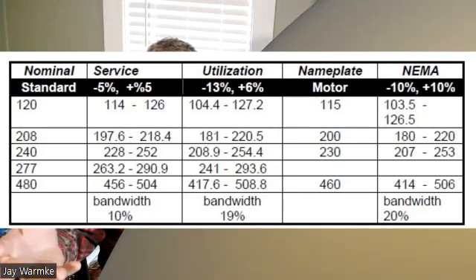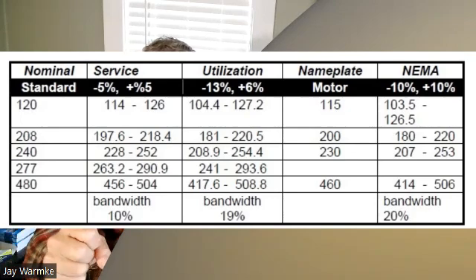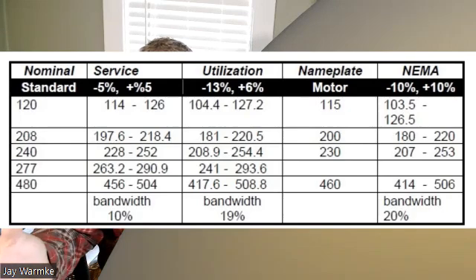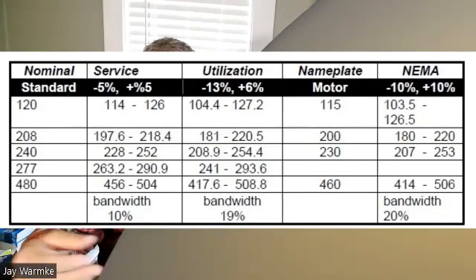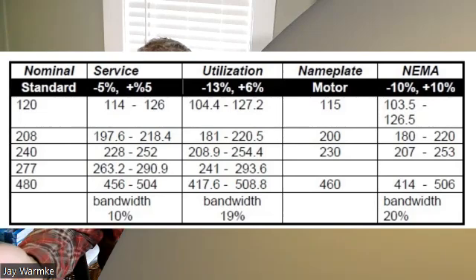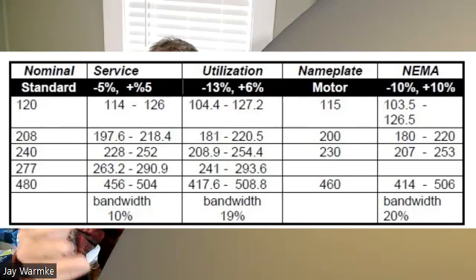And the NEMA for operating appliances and the like say that your appliances should tolerate a plus or minus 10% and still function. But obviously there's a sweet spot that they want to operate within. So that's pretty much what we're talking about there for motors and the like. So hopefully your refrigerator won't be damaged if it's operating anywhere within a plus or minus 10% of its nominal operating voltage. Jay. Yeah, Joe.